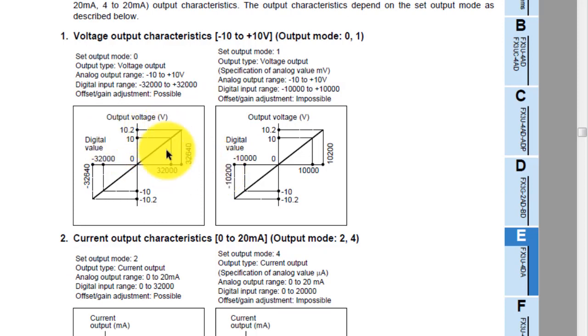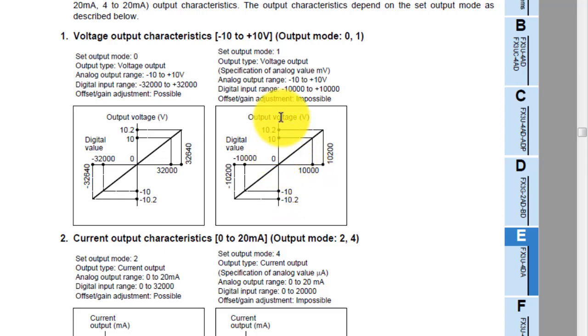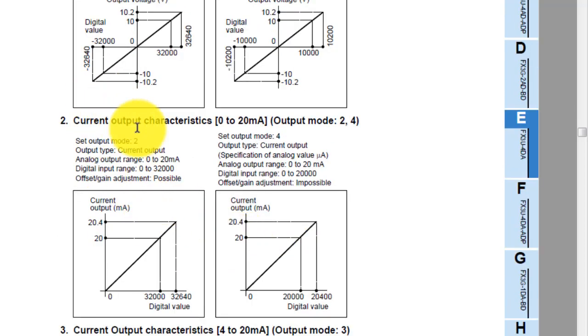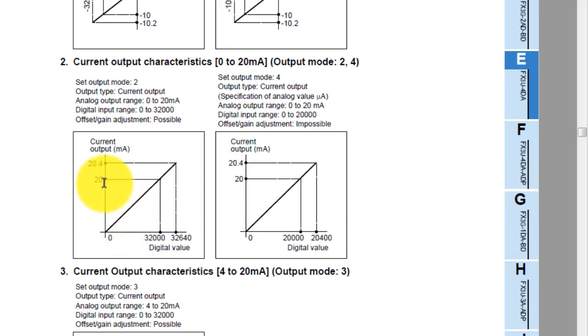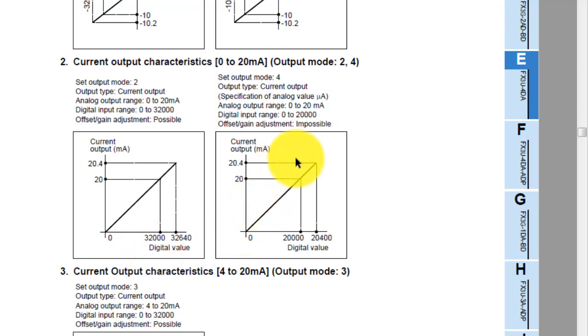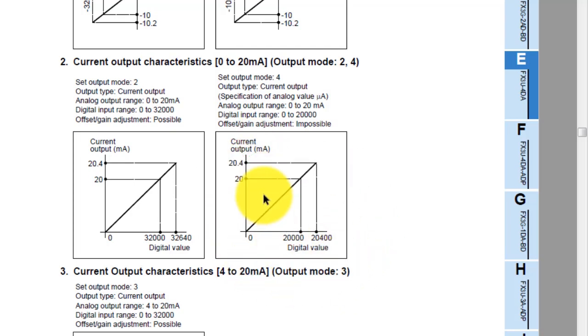You can see the maximum digital value for 10 volt output is 32,000. For current mode, maximum 20mA corresponds to a digital value of 32,000, or 20.4mA at the upper limit. The same concept applies across the output graph modes.